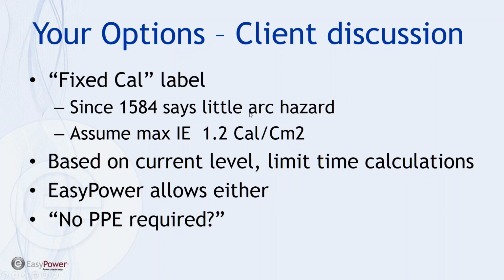Since 1584 is pretty vague about arc flash at those voltages, and says in essence you can disregard those low energy systems, one option may be just to fix the calorie label and say, okay, assume that the maximum calorie inside that panel is 1.2 calories per square centimeter. That needs to align with the client's corporate policy and how he's going to train people to recognize that system. And again, this is based upon the current level and the time calculations that we just looked at.